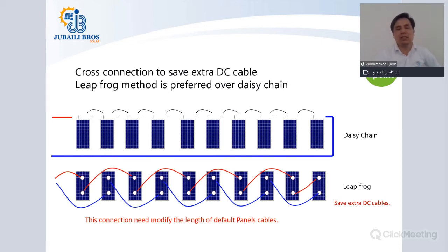This will lead to using extra DC cable. But if you are using a leapfrog type of connection, you will be connecting the first solar panel to the third, the third to the fifth, fifth to the seventh, and accordingly you will be bringing back by putting a spacing between each solar panel. In this way, your positive and negative terminals will be at one end, which will lead to decreased solar cable. So if you have a big power plant, these DC cable savings would be a lot for you.